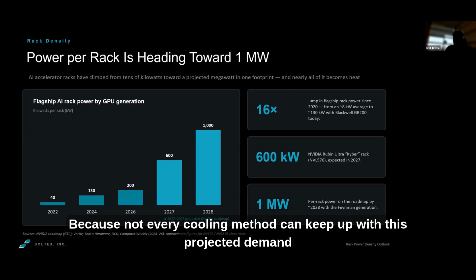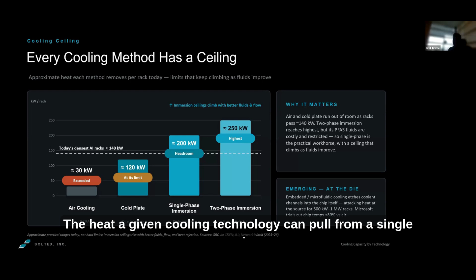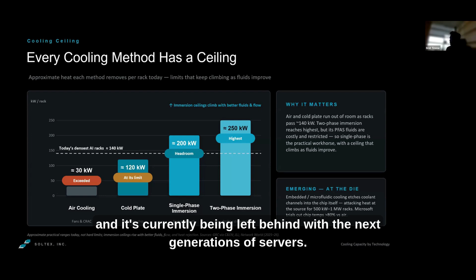This depicts the different cooling technologies employed in systems today and in future systems. Each bar is the approximate heat a given cooling technology can pull from a single rack, and the dashed line is today's densest AI rack at about 130 to 140 kilowatts per rack. Air cooling tops around 30 kilowatts per rack, and it's currently being left behind with the next generations of servers.